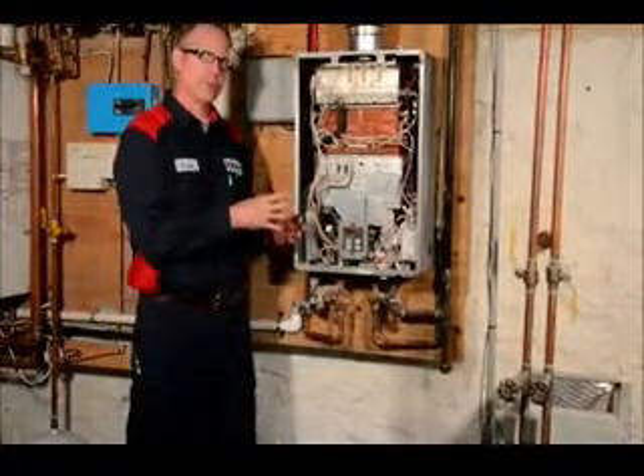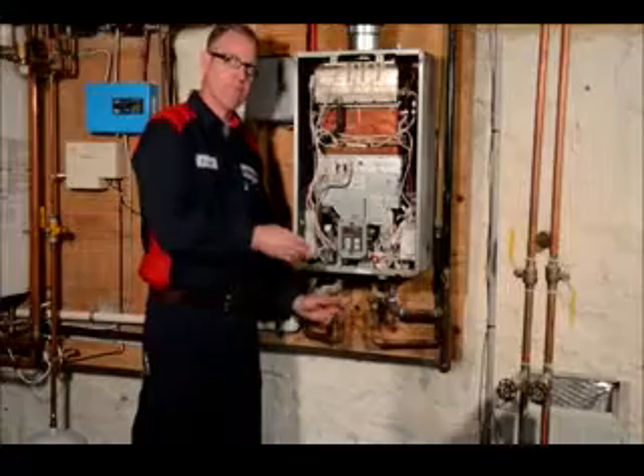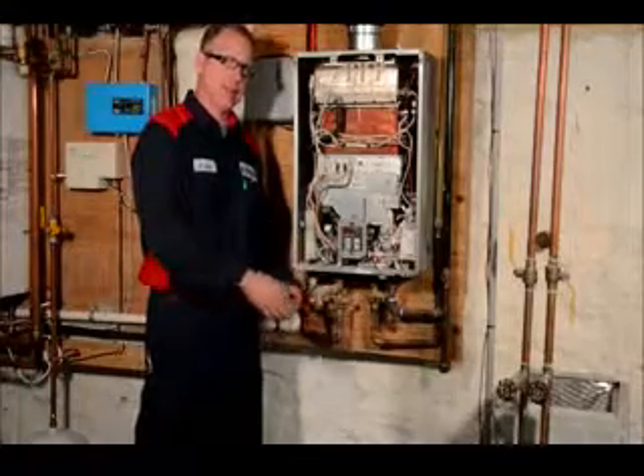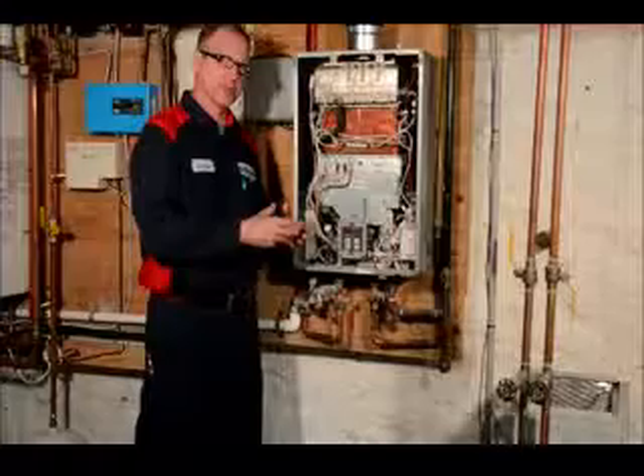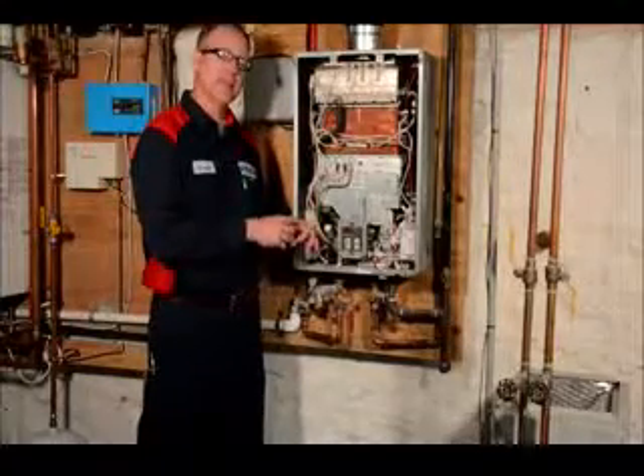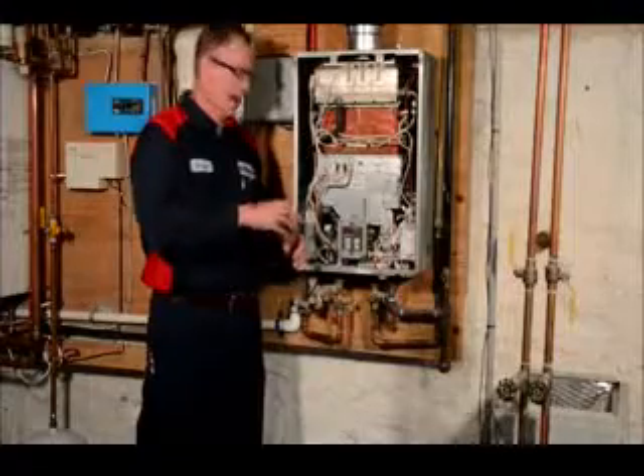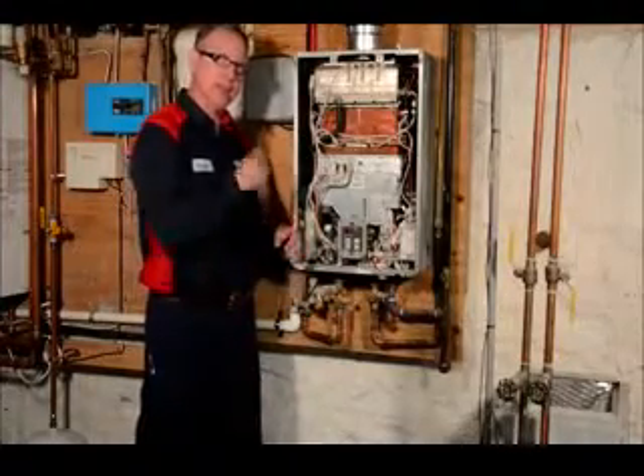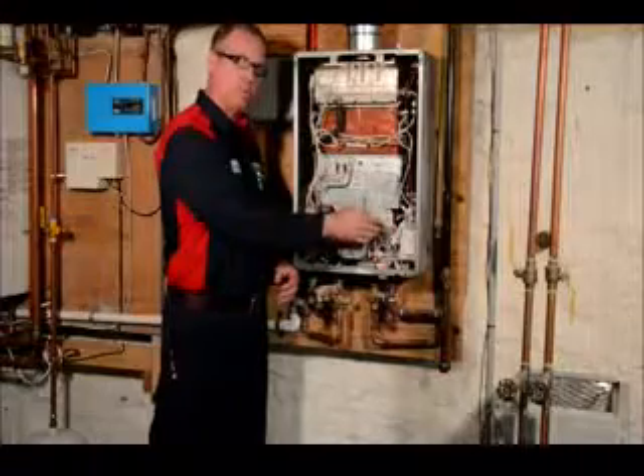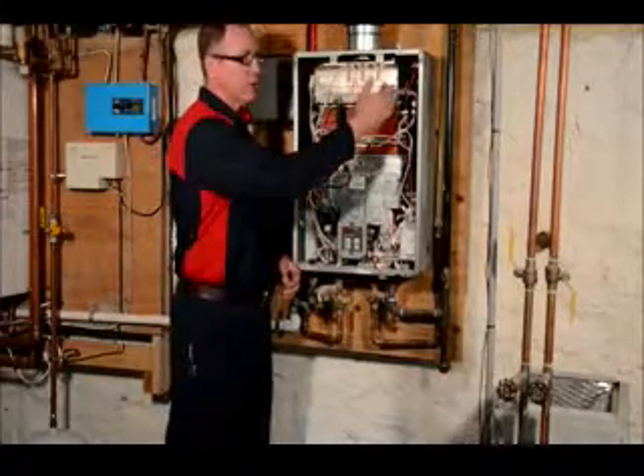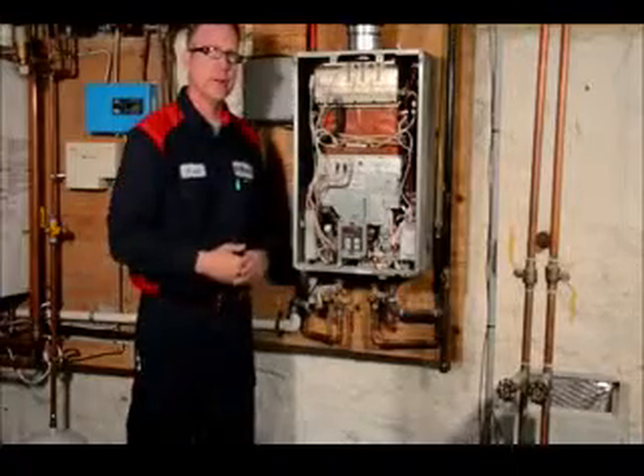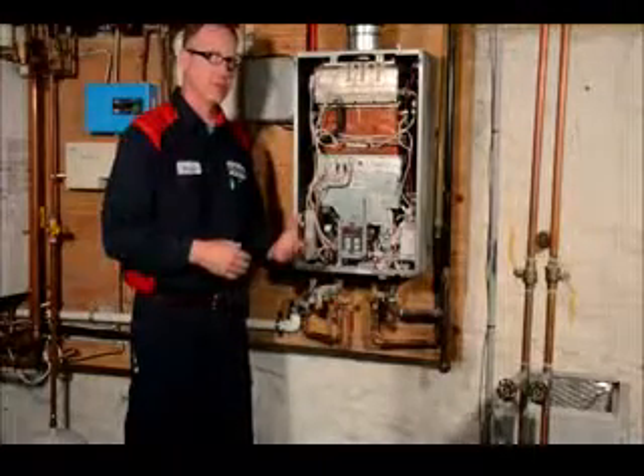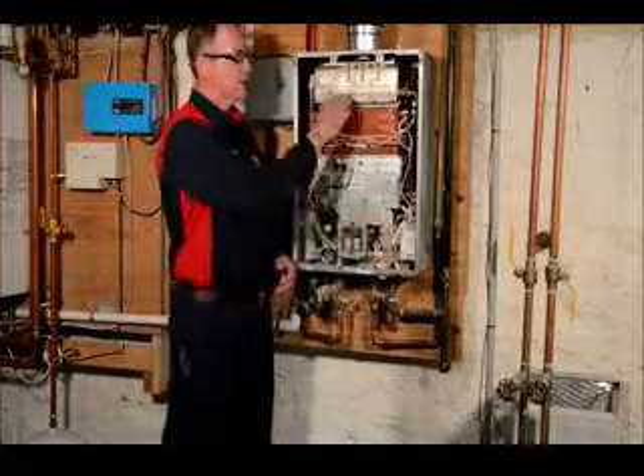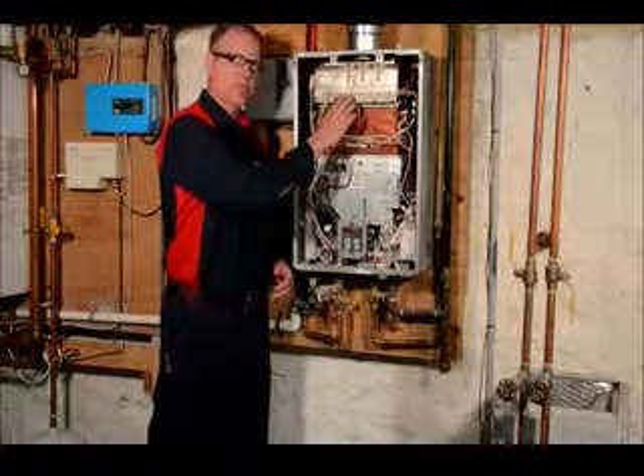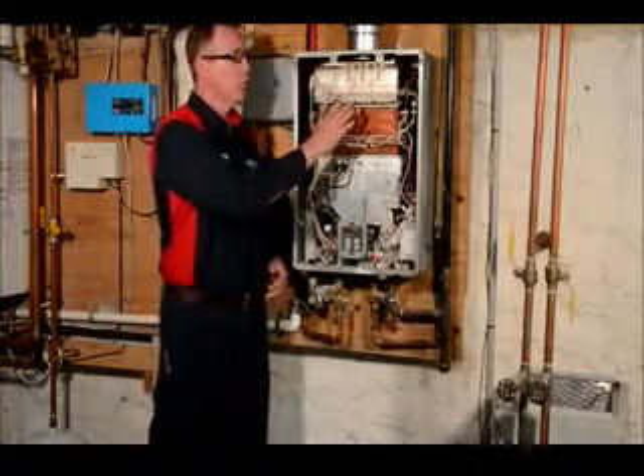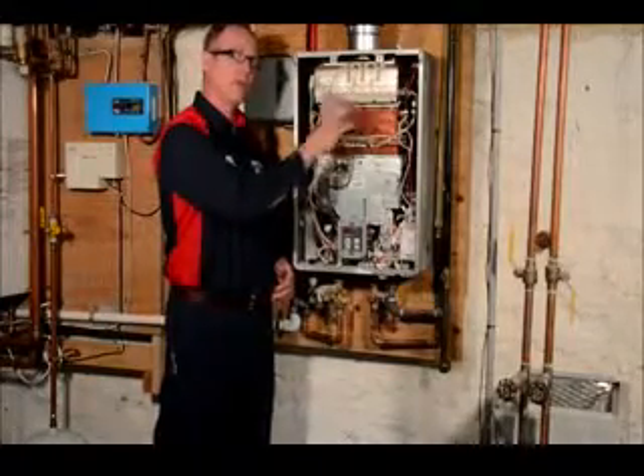How the Rinnai tankless water heater works: it has a flow sensor on the bottom of it for incoming water. As the incoming water goes through, the flow sensor has magnets that are embedded in the impeller that spin. As the flow sensor spins, the magnets spin and communicate the revolutions to the control board, which are also monitored by an incoming thermistor that's monitoring the incoming water temperature. From the thermistor, the water strikes the first heat exchanger, which is a stainless steel condensing heat exchanger, where the exhaust gases pass. And that is why this is so efficient.